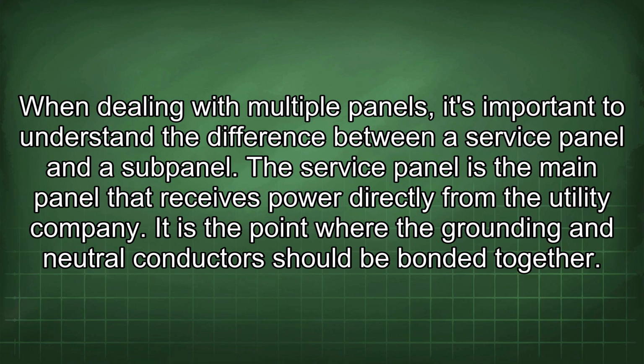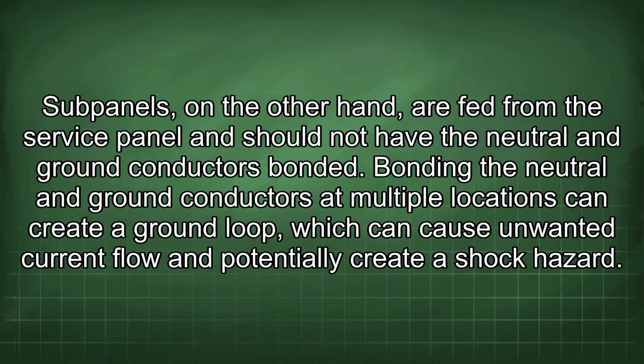When dealing with multiple panels, it's important to understand the difference between a service panel and a subpanel. The service panel is the main panel that receives power directly from the utility company. It is the point where the grounding and neutral conductors should be bonded together. Subpanels, on the other hand, are fed from the service panel and should not have the neutral and ground conductors bonded. Bonding the neutral and ground conductors at multiple locations can create a ground loop, which can cause unwanted current flow and potentially create a shock hazard.